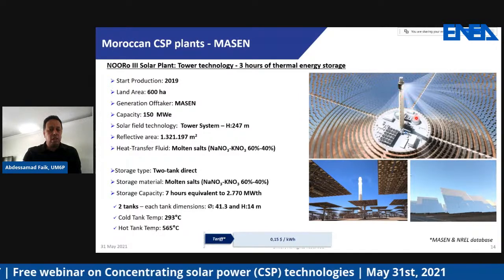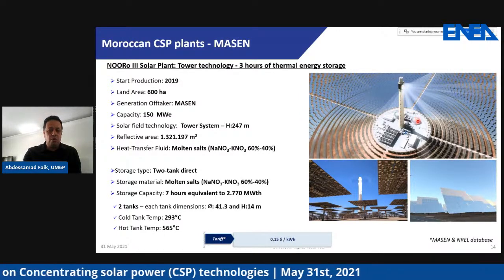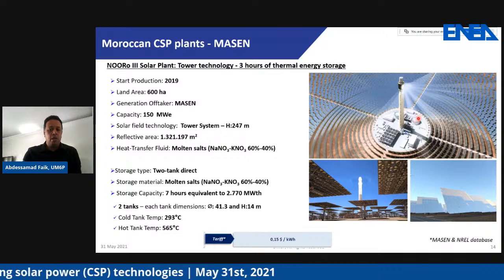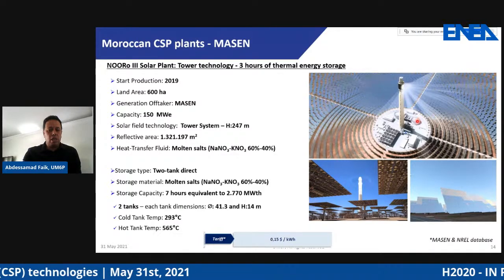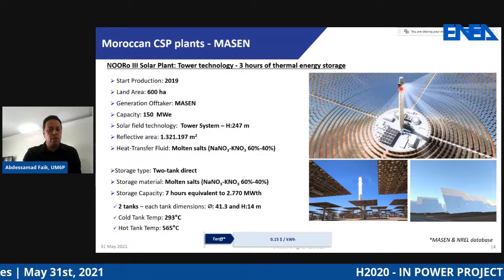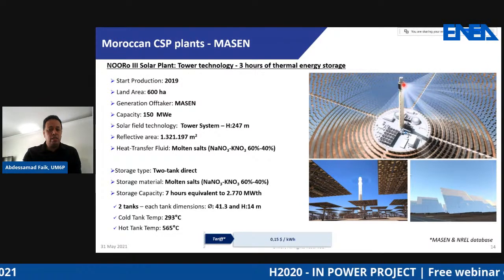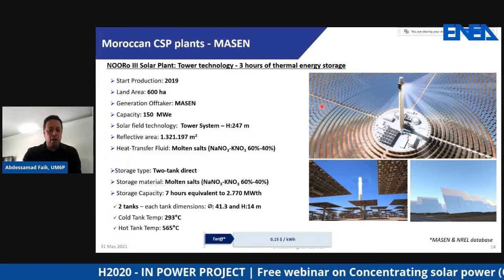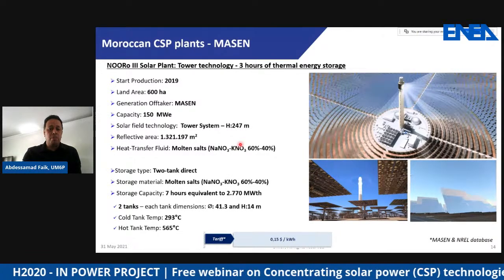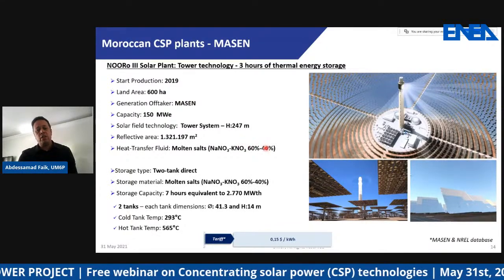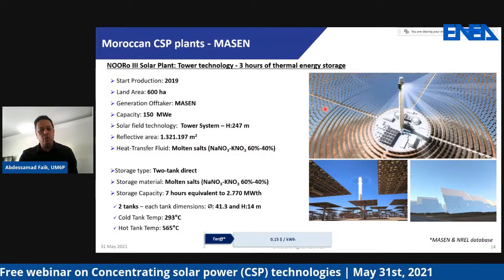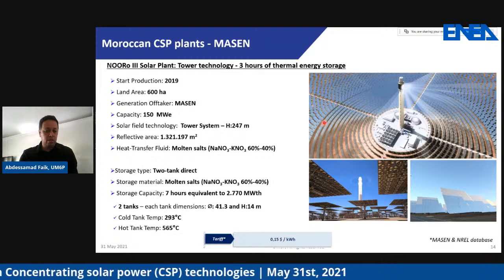In the morning, when we are operating the power plant, we inject the salt from the cold tank to the top of the receiver to collect heat and charge it. But in this case, we go to a higher temperature, because in the parabolic trough system, the decomposition temperature of the oil used in the solar field is around 400 degrees C.